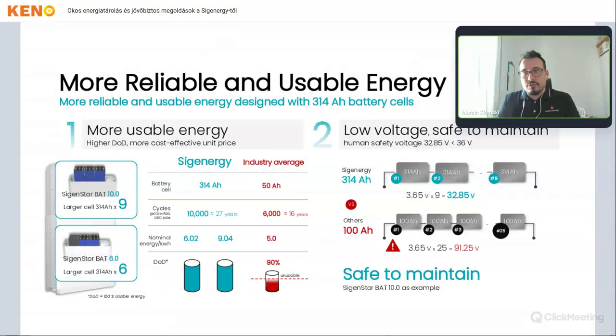Just to give an example, if we do one charge and discharge cycle per day, that's 3,000 cycles in 10 years, so 10,000 cycles can really be like 27 years. This is a long lifetime per battery, and generally it can provide full usable capacity, full depth of discharge, so you can utilize 100% of that.